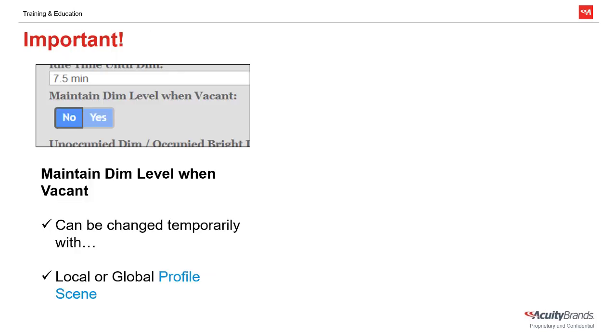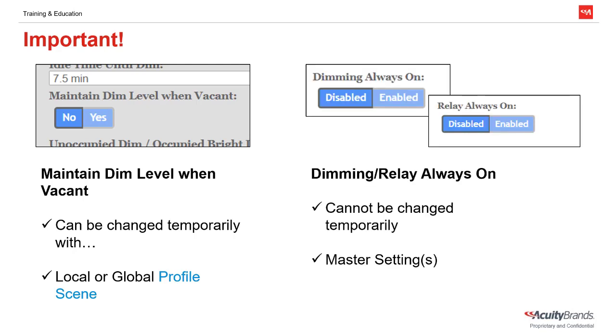Now that we've learned the functions of these settings, let's discuss one more major difference between them. Maintain Dim Level When Vacant can be changed temporarily through the use of a local or global profile scene, meaning the device behavior can change throughout the day or on demand with a button press. Conversely, Dimming Always On and Relay Always On are master settings of the device; therefore they cannot be changed temporarily. They can only be changed through Sensor View and will remain until changed in the default settings tab.